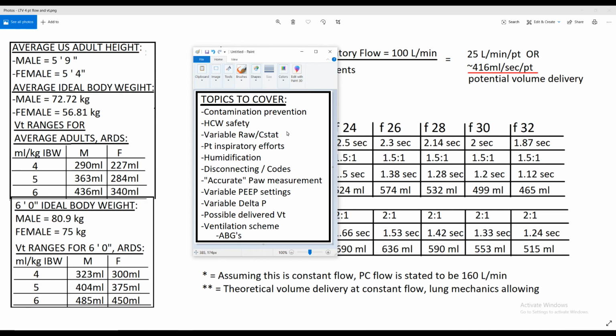The variable airway resistance and C-stat, we're sort of addressing that issue because we're going to use pressure control. I think we can agree that if we used volume control on 4 patients connected to the same ventilator, if they had anything but the exact same resistance and compliance and they were all about the same size, that would have disastrous results. So the way we can get around that, all the patients having variable resistances and compliances, is instead of targeting volume on the breath delivery, we just target pressure.